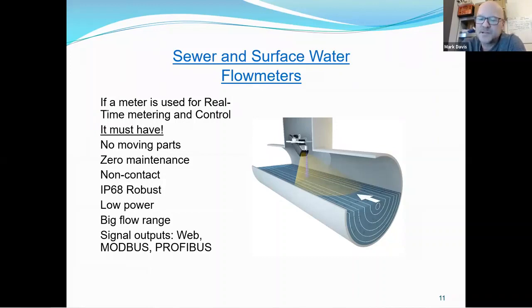That's very important with a sewer network, obviously, because you get surcharging with high flow events. Ideally, it should be low power, so it can be powered by solar power or what Knut's going to be talking about. Very wide flow range. I'll give you some examples of the type of flow ranges that we're looking at using the same piece of equipment. And of course, the outputs should be compatible with your telemetry. So ideally Modbus, Profibus, web-enabled as well, which will also give you real-time data and diagnostic information, which is very important.